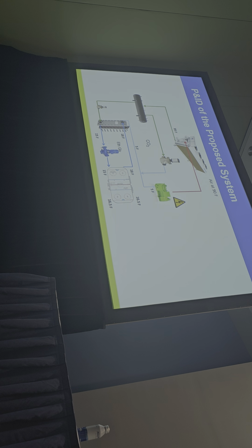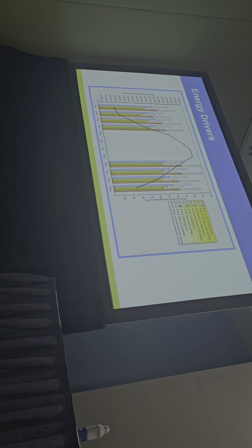The only difference, and if you look at this diagram, you can see that the outlet of the gas cooler is going into a flash tank. And this is probably the biggest difference in a CO2 system compared to any other system. In this case, we're going in there indirect with the glycol in the floor. We're already using glycol, and we kept the same floor, and we kept glycol in the floor.